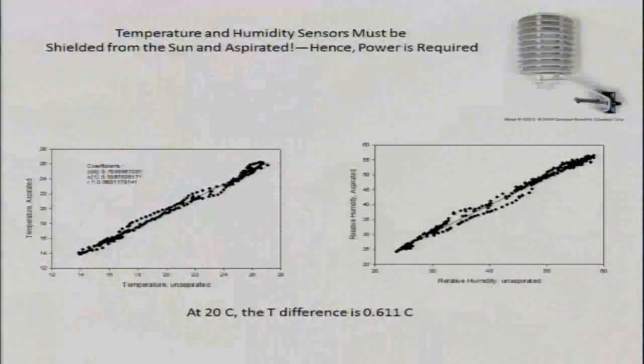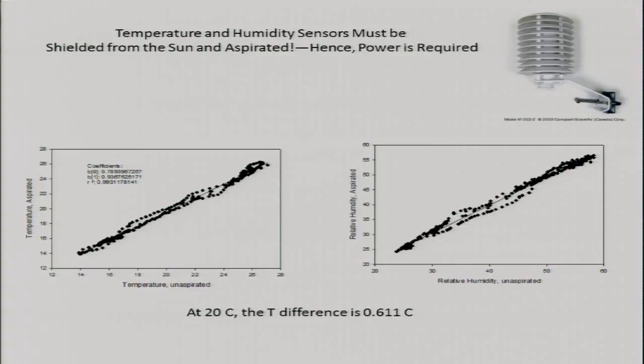The other point gets back to what you're measuring. It's really, really important to aspirate and shield the sensor. Otherwise, you're just measuring the temperature of the sensor itself. I've had my students over the years take some thermometers in the lab, some unaspirated, some aspirated, and compare them. You can see some hysteresis, and the slope is about 0.93, so about 7% error. At 20 degrees, there's a bias of over half a degree, 0.6, just from how the sensor is deployed.